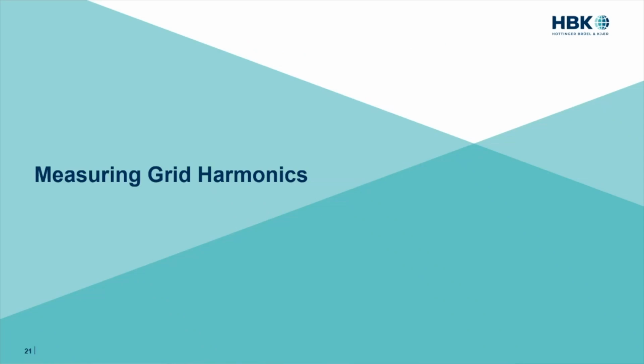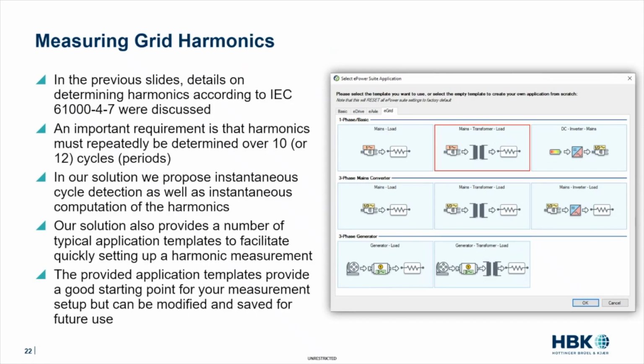Okay, then we go into measuring grid harmonics. How do we do that? Well, in our solution we have implemented all those functionalities such that it can be very easily used. In our solution, of course, we follow the standards. So every time we measure 10 cycles, and then we generate the harmonics. We do that based on a technique called cycle detection. So we measure 10 cycles and generate the harmonics, and then we measure the next 10 cycles and generate the harmonics. But for the user, all this is made very, very easy.